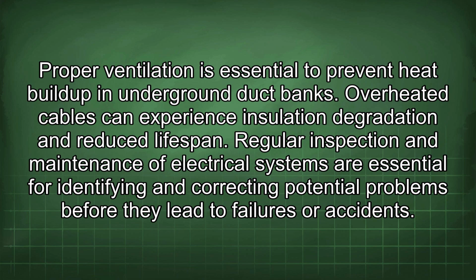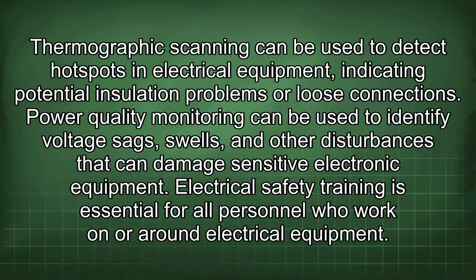Regular inspection and maintenance of electrical systems are essential for identifying and correcting potential problems before they lead to failures or accidents. Thermographic scanning can be used to detect hotspots in electrical equipment, indicating potential insulation problems or loose connections. Power quality monitoring can be used to identify voltage sags, swells, and other disturbances that can damage sensitive electronic equipment.